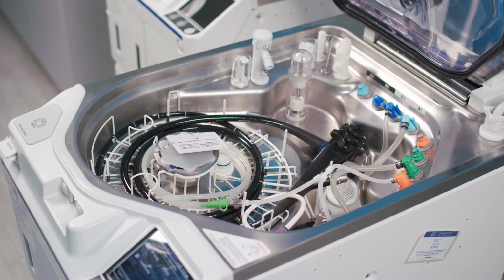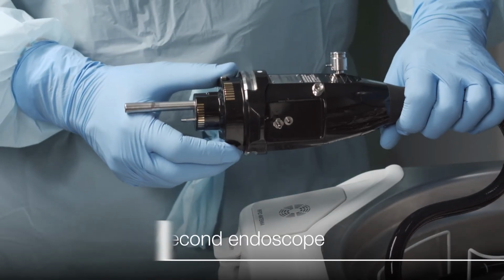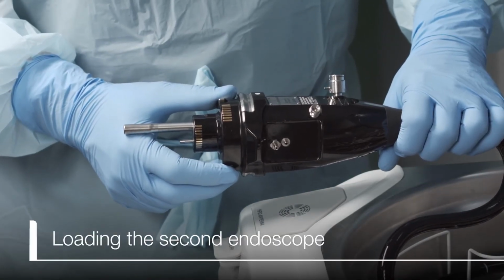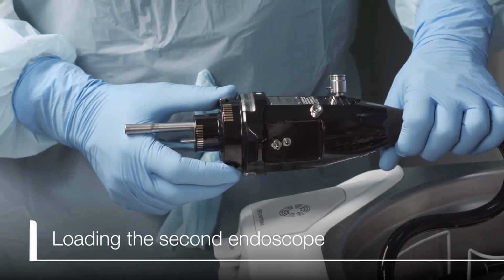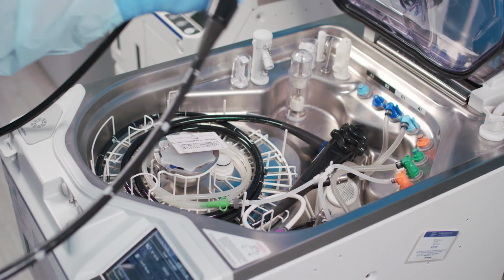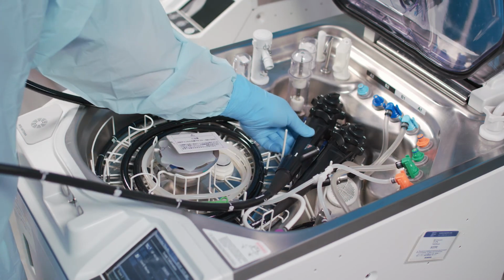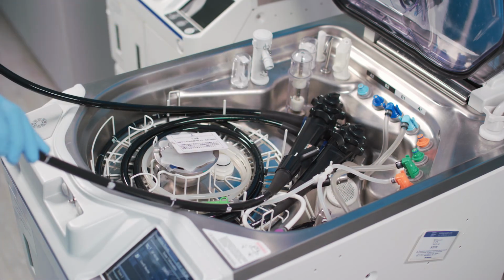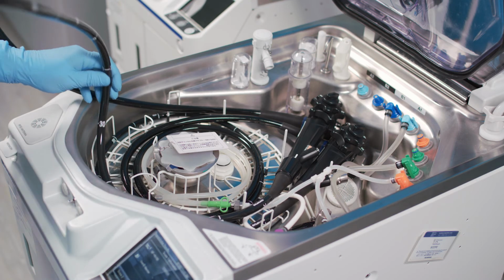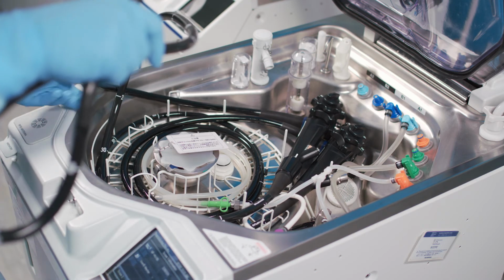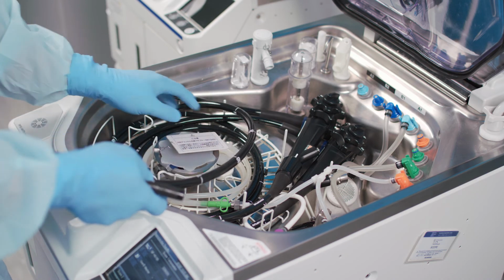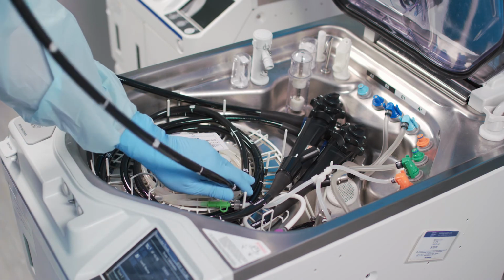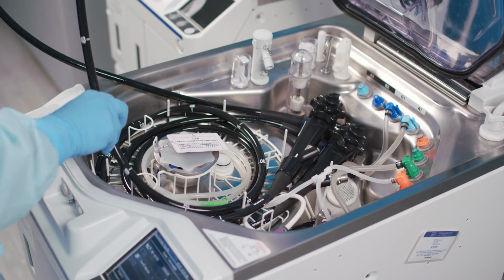The OER-Elite can reprocess 2 endoscopes at the same time. Please refer to the list of compatible endoscopes and connecting tubes. First, scan the scope RFID or RFID tag over the OER-Elite ID reader section. Next, place the second endoscope's control body directly to the left side of the first loaded scope. The insertion tube of the second endoscope is loaded the exact same way as the first endoscope, following the same path around the retaining rack.